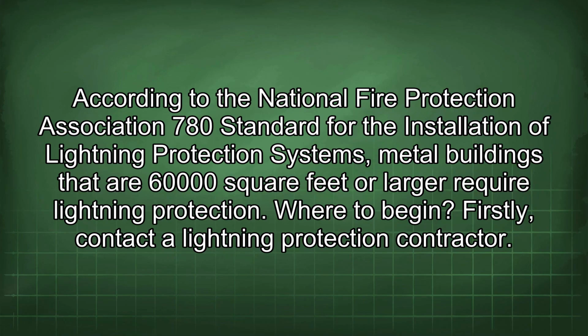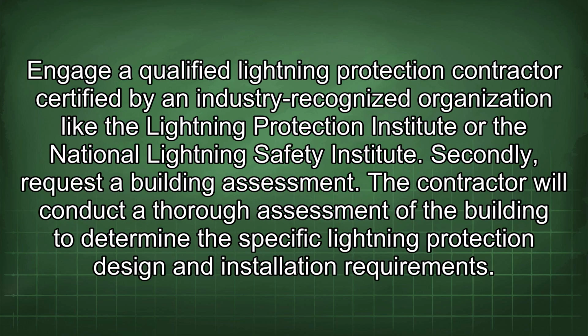According to the National Fire Protection Association 780 standard for the installation of lightning protection systems, metal buildings that are 60,000 square feet or larger require lightning protection. Where to begin? Firstly, contact a lightning protection contractor. Engage a qualified lightning protection contractor certified by an industry-recognized organization like the Lightning Protection Institute or the National Lightning Safety Institute. Secondly, request a building assessment.